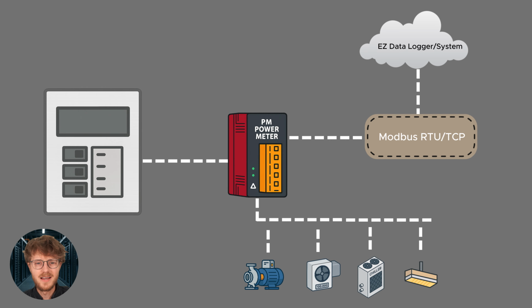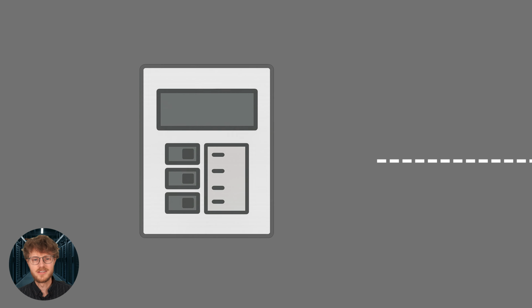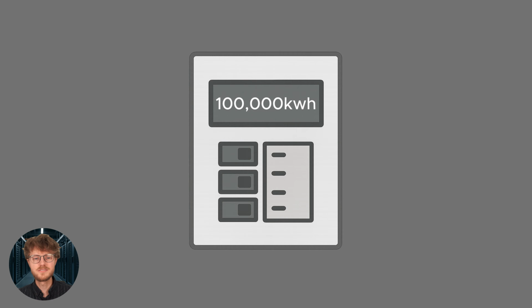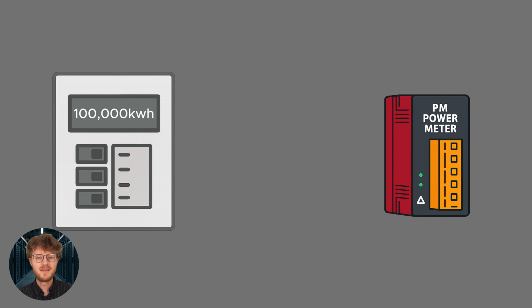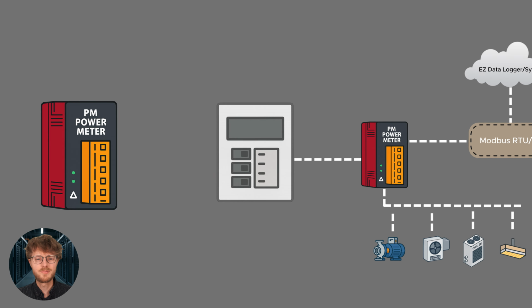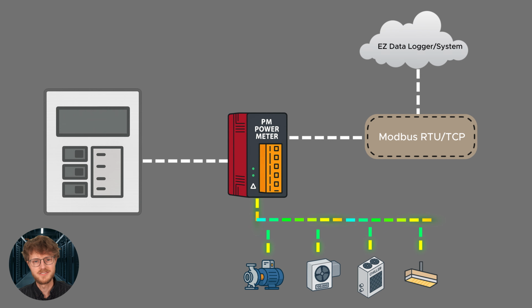At the simplest level, a PM power meter is a device that connects to your electrical circuits and measures how much energy they're consuming in real time. Think of your main electrical panel. It shows you the total energy for the entire facility. A PM power meter goes one step deeper, breaking that down circuit by circuit. That means instead of only seeing the big number, you can see where the energy is actually going, whether it's to your chillers, pumps, fans, lighting, or even specific racks.